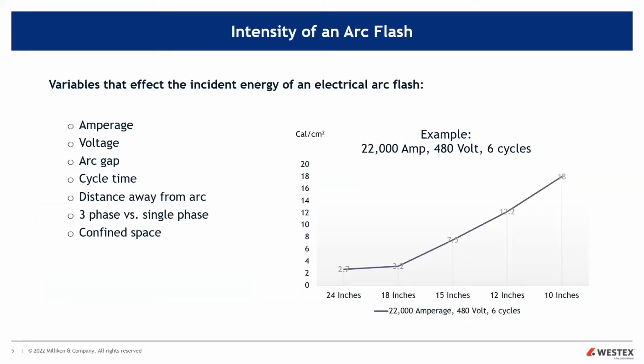So I think everyone's familiar with big arcs and small arcs. They are all measured in calories per square centimeter, as we all know. Of course, the key variables that dictate if the incident energy is going to be large or small are the factors on the left. The big ones, of course, are the amperage, the available fault current. Obviously, the higher the available fault current, the higher the arc energy, the incident energy if there's an arc flash.